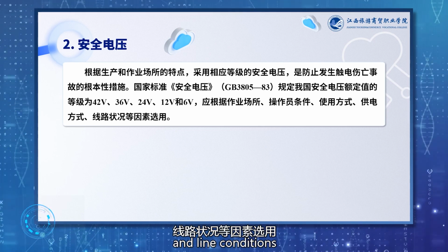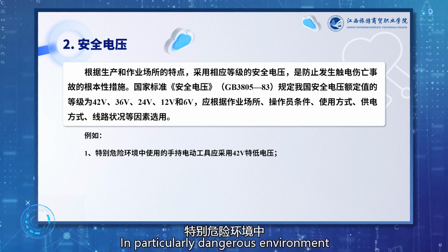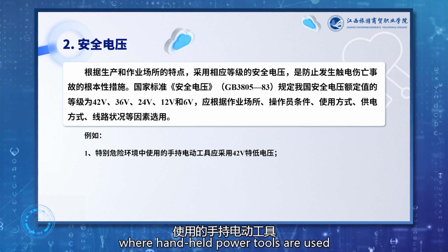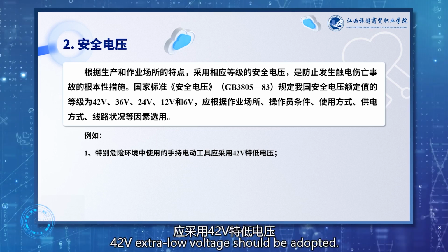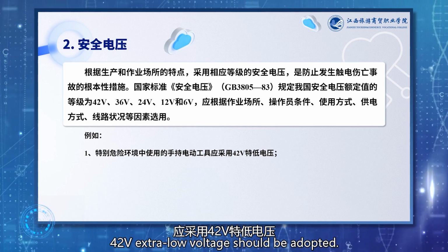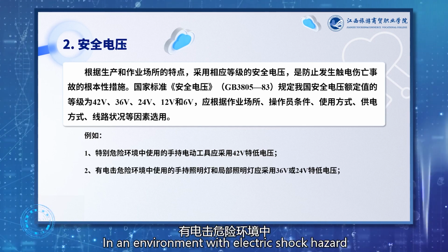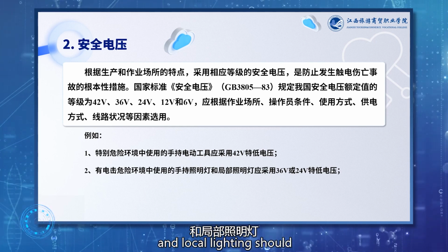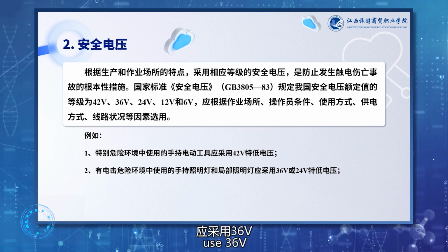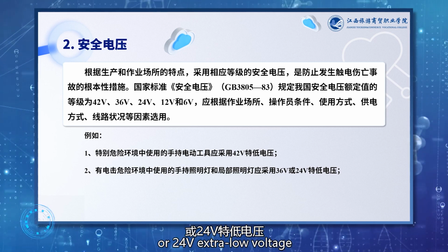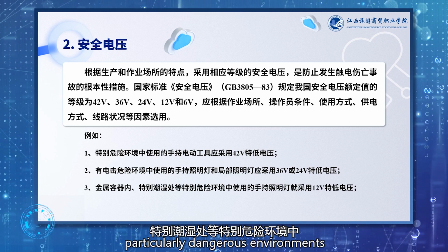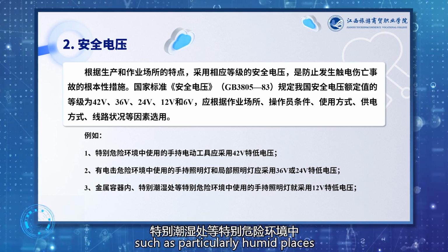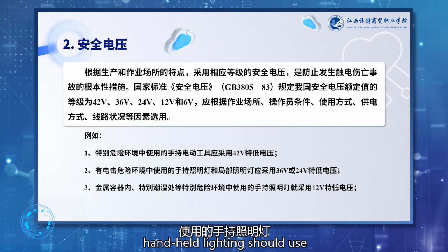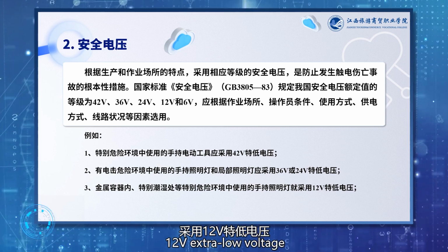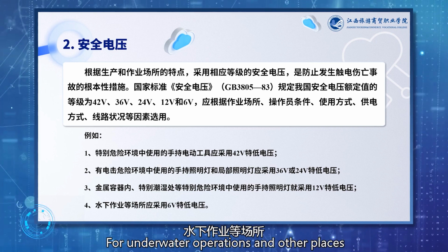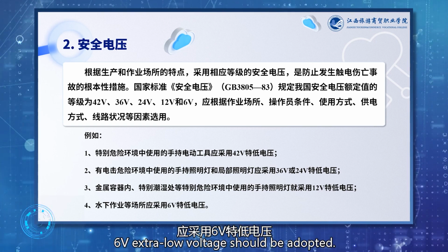For example, in particularly dangerous environments where handheld power tools are used, 42V extra low voltage should be adopted. In an environment with electric shock hazard, handheld lighting and local lighting should use 36V or 24V extra low voltage. In a metal container, or particularly dangerous environments such as particularly humid places, handheld lighting should use 12V extra low voltage. For underwater operations and other places, 6V extra low voltage should be adopted.